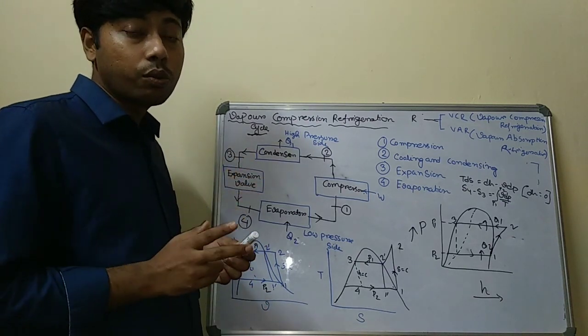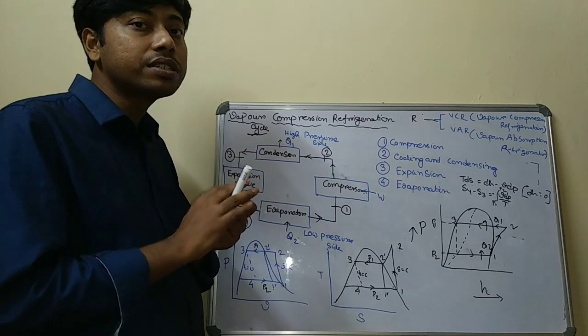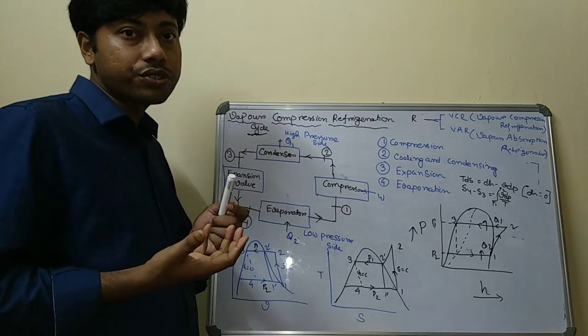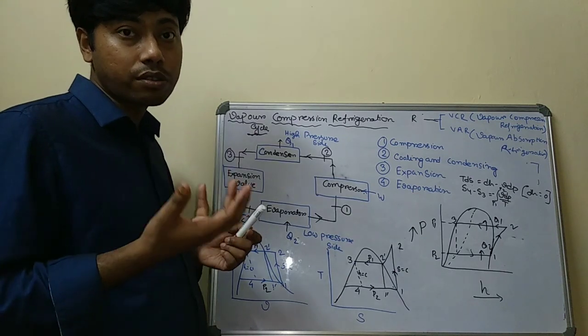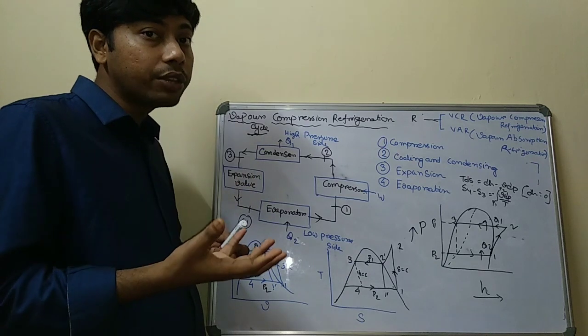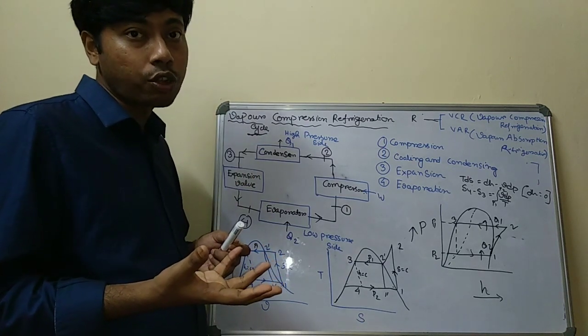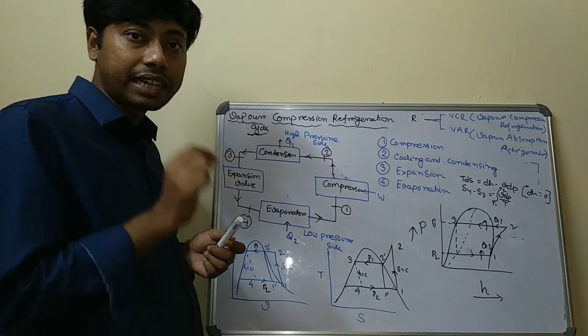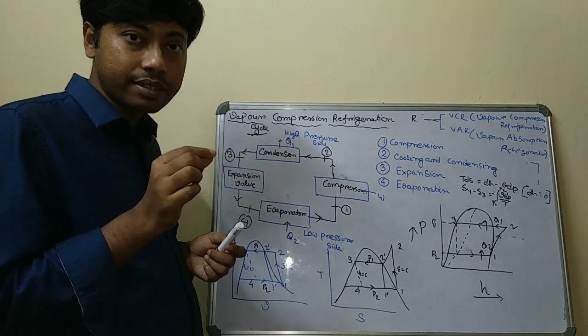But between dry compression and wet compression, dry compression is far better, because wet compression is very dangerous for the compressor or piston cylinder assembly. There is some liquid refrigerant present in wet compression, and that liquid refrigerant, or liquid droplets, can damage the cylinder piston assembly.